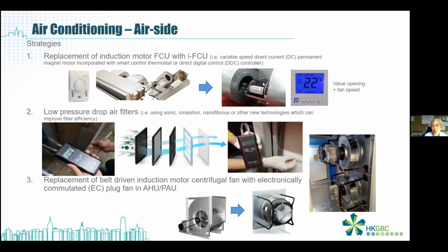This kind of fan coil unit system uses variable speed DC motors. They control the room temperature not only by using the solenoid valve, they also use the fan speed. So fan speed and valve together control the space temperature. The benefit is that when you use both parameters together, most of the time the fan speed can be lower. In the conventional one, you need to do it manually, but most people would not activate the fan speed, and the control of the temperature is not precise. This is the problem. So when you use the smart fan coil unit system, you can save around 14 to 15% of the energy of the air side system.